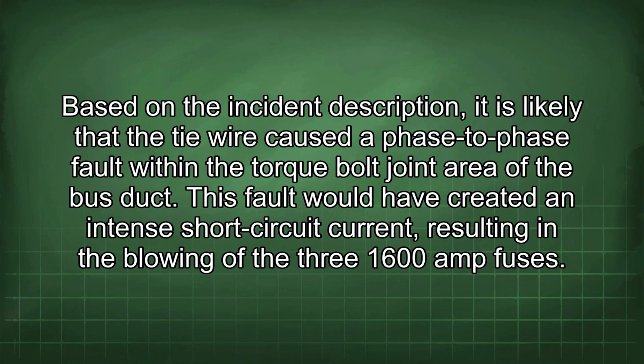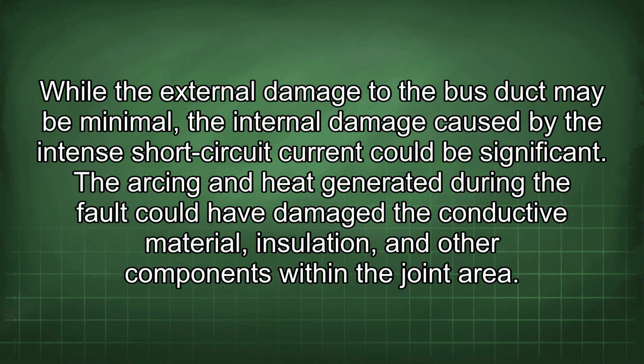Based on the incident description, it is likely that the tie wire caused a phase-to-phase fault within the torque bolt joint area of the bus duct. This fault would have created an intense short-circuit current, resulting in the blowing of the three 1600 amp fuses. While the external damage to the bus duct may be minimal, the internal damage caused by the intense short-circuit current could be significant. The arcing and heat generated during the fault could have damaged the conductive material, insulation, and other components within the joint area.